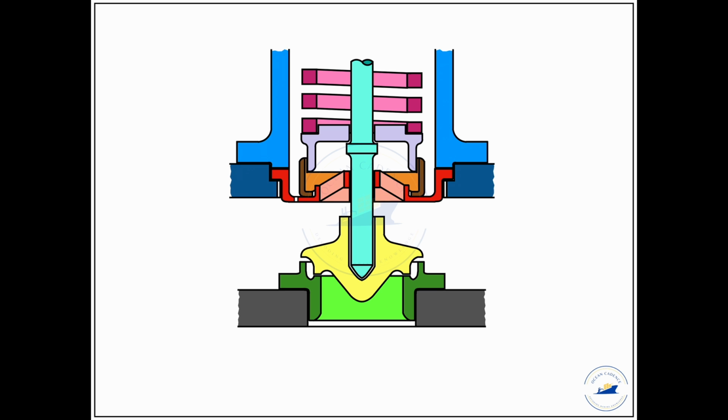The easing gear of the safety valve has to be removed from its place and the safety valve foundation has to be slackened, given that the boiler is already at atmospheric pressure and there is no buildup of pressure inside the boiler, and that has been witnessed. Once the valve is slackened from the foundation, the entire structure has to be brought into the workshop, and let us discuss the areas that are of particular focus.